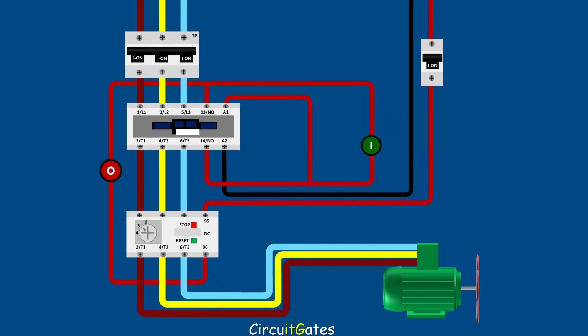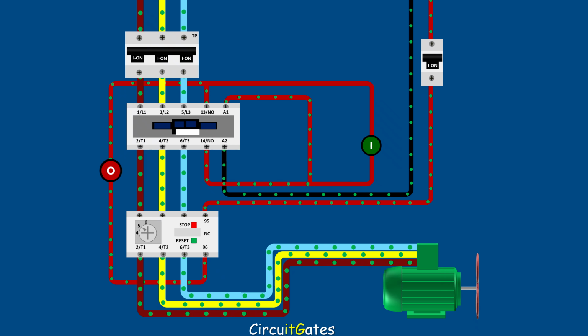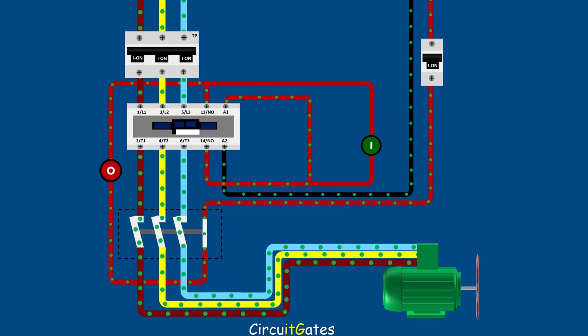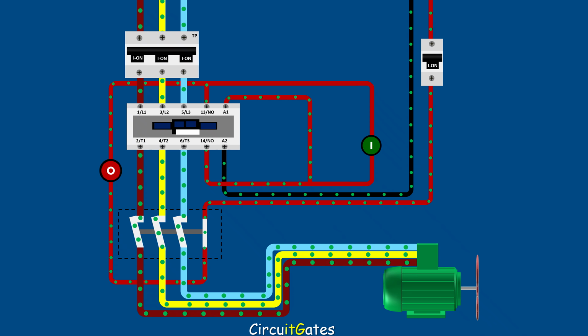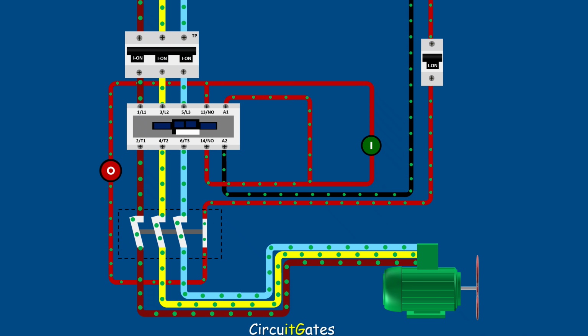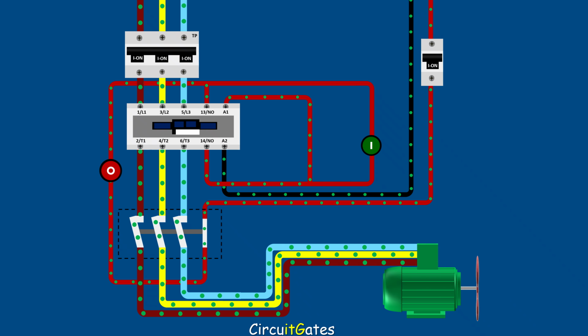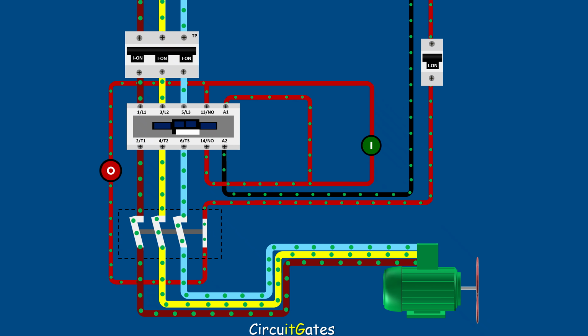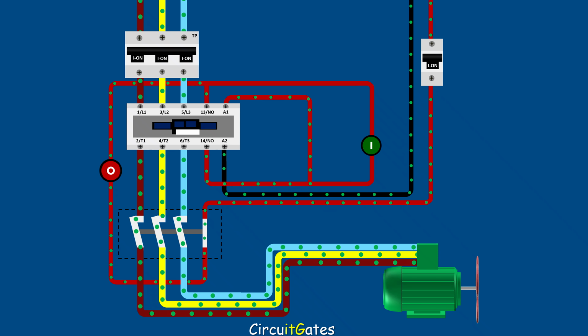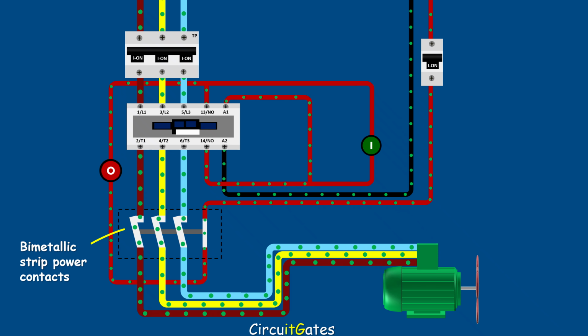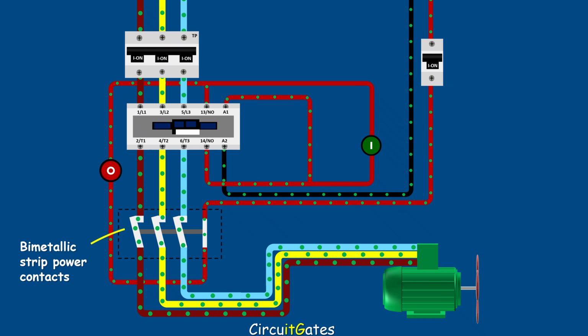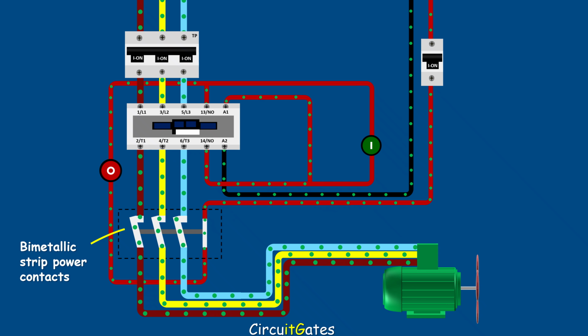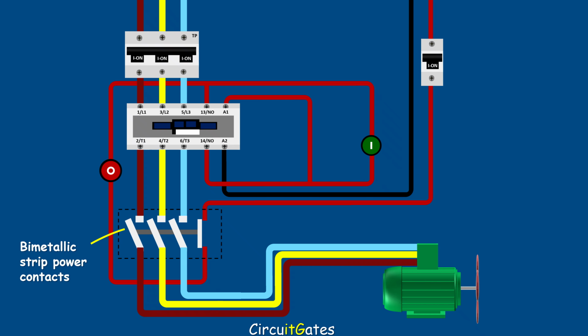Small overcurrent conditions due to overload result in overheating of the electric motor. When the electric motor overheats, the insulation covering the windings will be damaged, and there will be a direct contact between the windings, which is a short circuit in the windings, resulting in burning of the electric motor. The overload relay switches off the circuit in the event of an overload, which causes overheating of the electric motor. One type of overload relay has bimetallic strip power contacts that, when excess current flows through them, heat up and bend, breaking the circuit. The bending of power contacts opens the control circuit contact, powering off the control circuit.